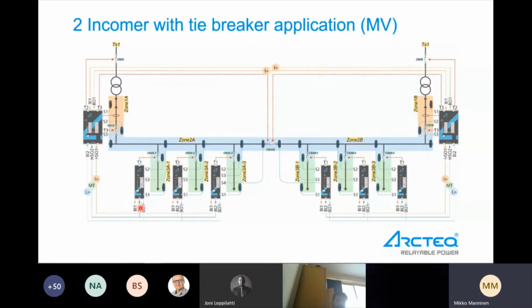But mostly medium voltage boards are built with the point sensors. That is the most typical application. It's one sensor for each closed compartment. So for example, if we have a cable compartment, circuit breaker compartment, and a segregated busbar compartment, then we need to have one sensor in each. And if the busbar compartment is open, then we need to have one sensor in every 3 meters, because the flash will travel very fast with the way of the energy. So in this case, we are sharing the current between the units. So it doesn't matter whether it is the incomer left side or incomer right side. Both of these units are measuring current. And this is a so-called light selective system.